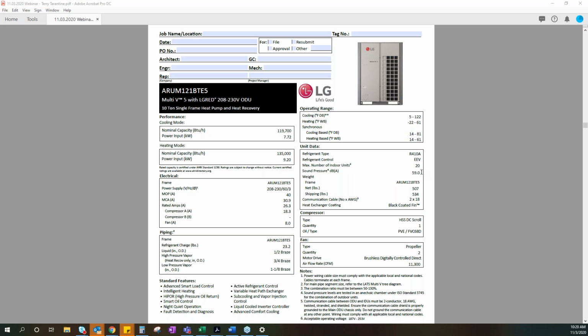Typically, we'll put these in old mechanical rooms where maybe there was an air handler and a boiler before, but very often we'll just put them right up on the roofs. And there may be concerns about sound levels for other occupants, neighboring buildings, maybe they want to put a patio on the roof. With these sound levels, we've done this successfully without any problems.